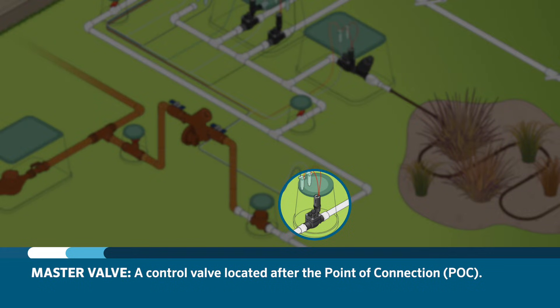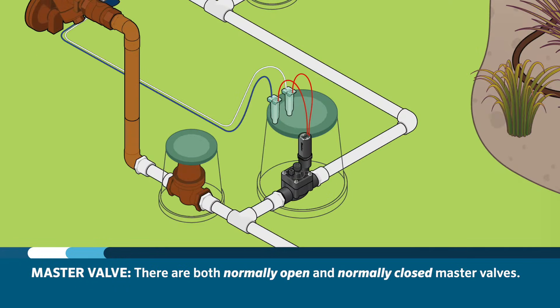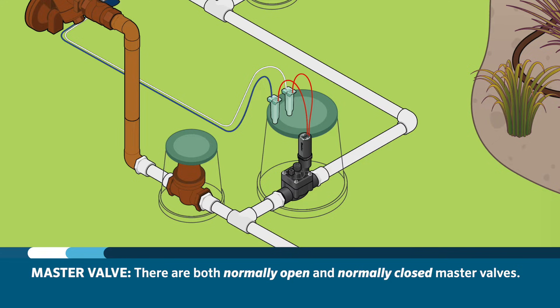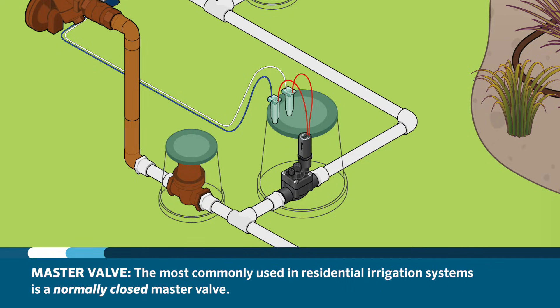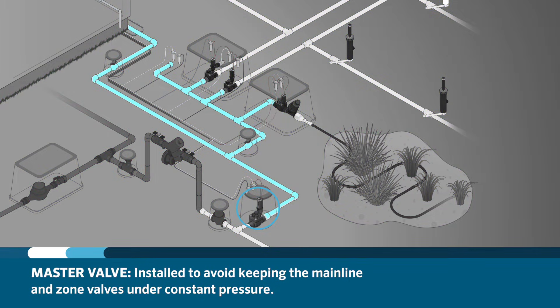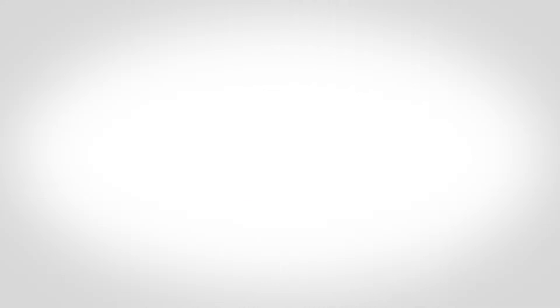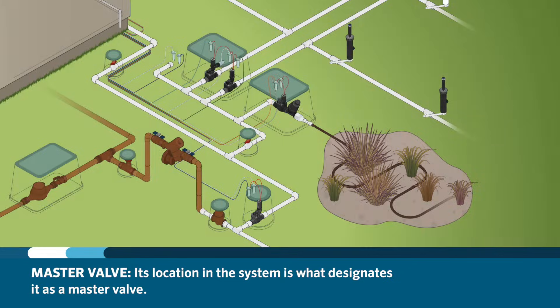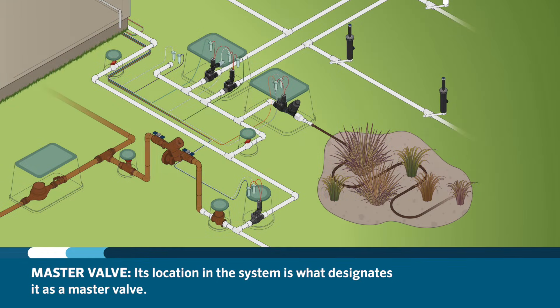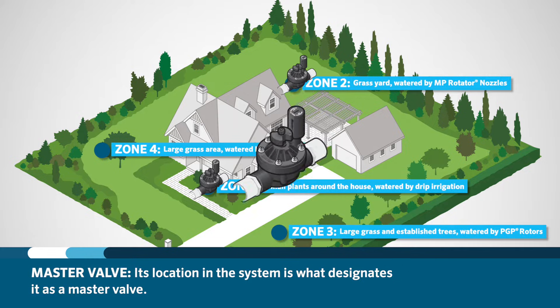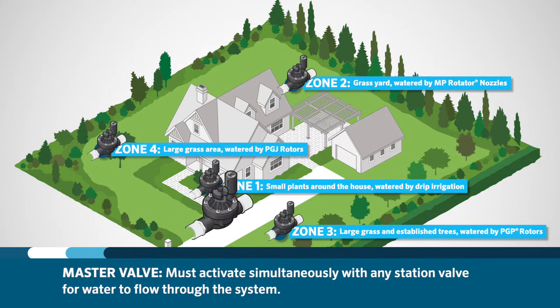After the pressure regulator, an optional and highly recommended device known as a master valve can be installed. The master valve in most cases is simply a control valve located after the POC. There are both normally open and normally closed master valves. Since a normally closed master valve is the one most commonly used in smaller irrigation systems, we will be referring to that type during this training. A master valve is installed to avoid keeping the mainline and zone valves under constant pressure, preventing damage created by irrigation mainline leaks. For example, you may use a Hunter ICV for both a station valve as well as a master valve. The master valve must activate simultaneously with any station valve for water to flow through the system.